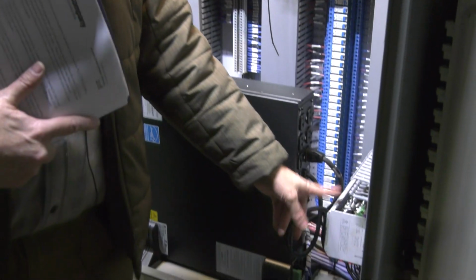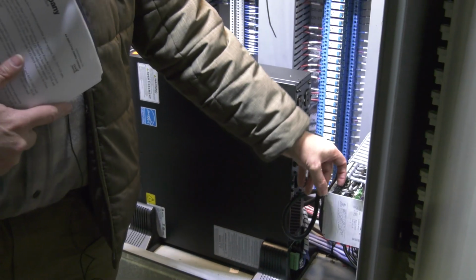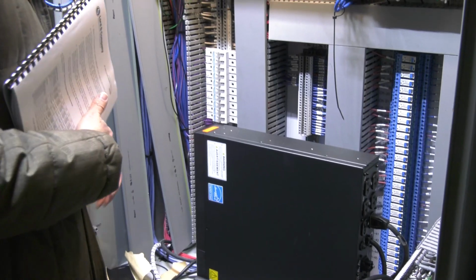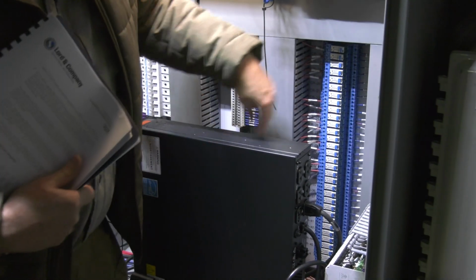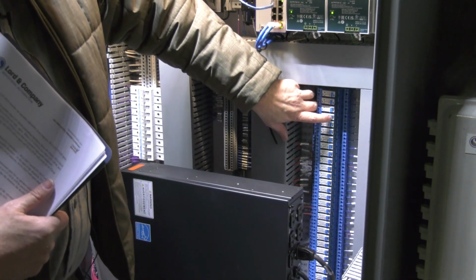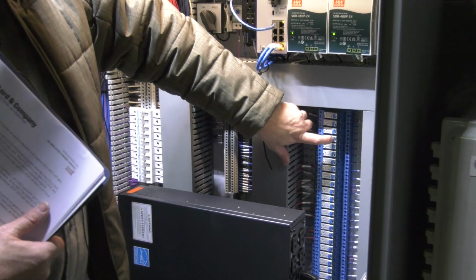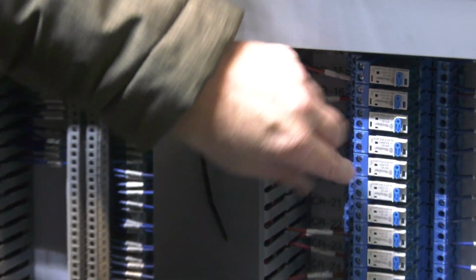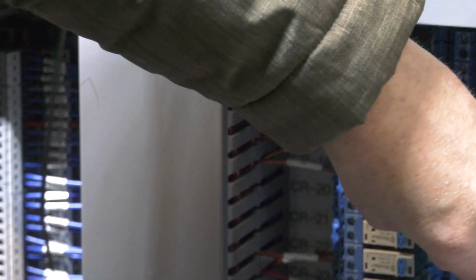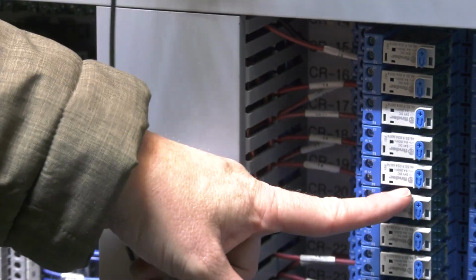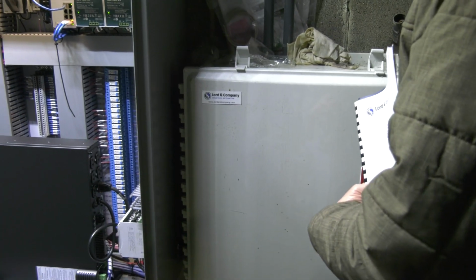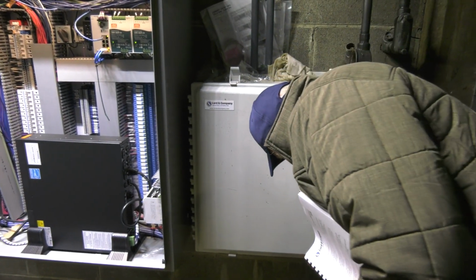Intrinsic safety barriers, if they need to be replaced, terminals do pop off, easy replacement, no configuration required. Your relays here, it's got an override. You can turn them on and off right here, or there's a little tab. You can break the tab and then twist the flag, and that relay will be on. Over here, let's see what we got here.